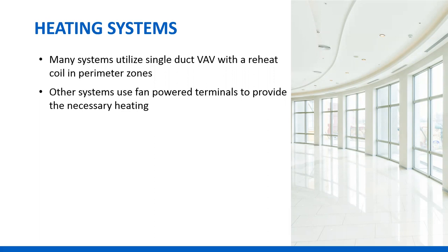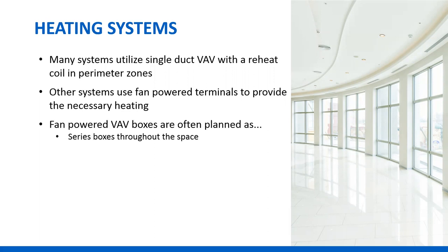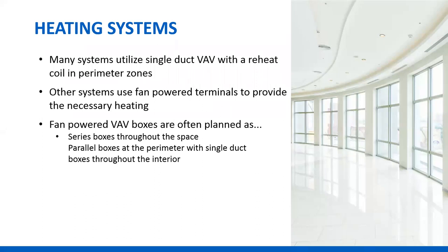Fan powered boxes come in two kinds: the series box and the parallel box. A series box has the fan on the discharge and is typically used throughout the space — Houston and Seattle are both series fan box towns. A parallel box has the fan running only when you need heat at the perimeter, with single duct boxes in the interior. That style is seen in Portland and Dallas. Apparently it's not a climate deal — it's a style thing about whether you're going to use series or parallel boxes.